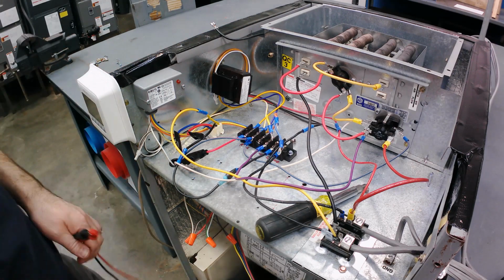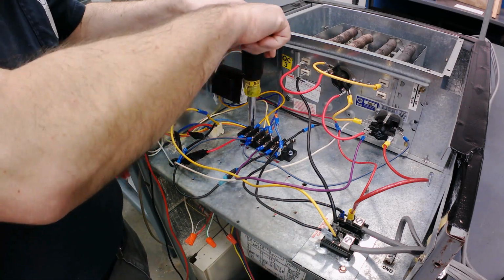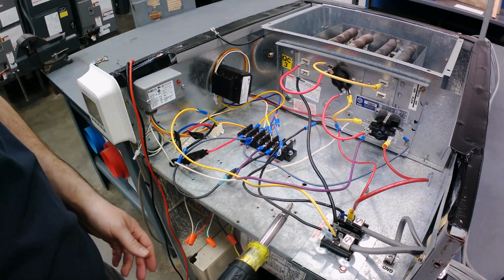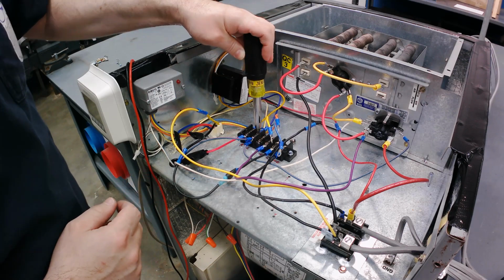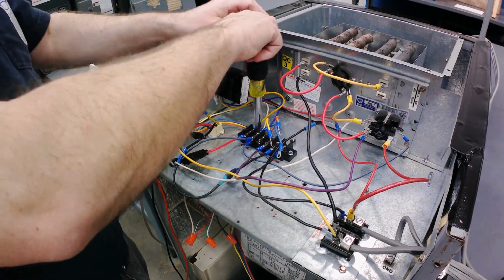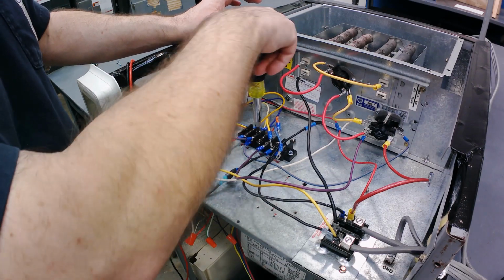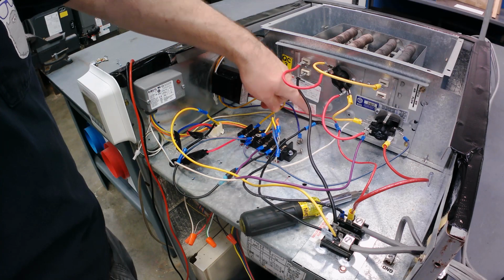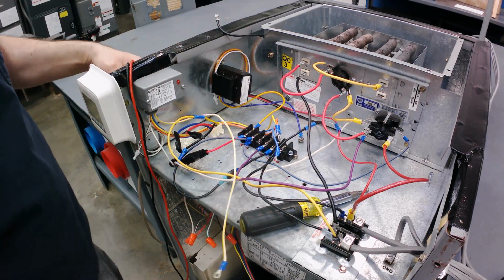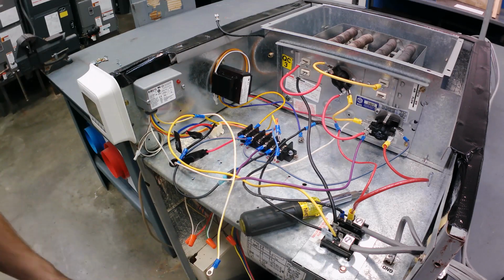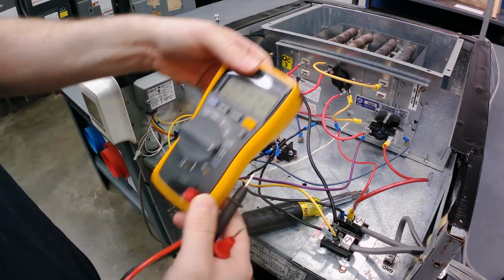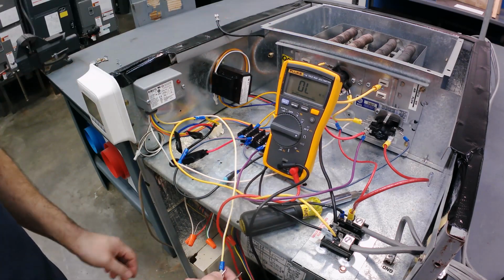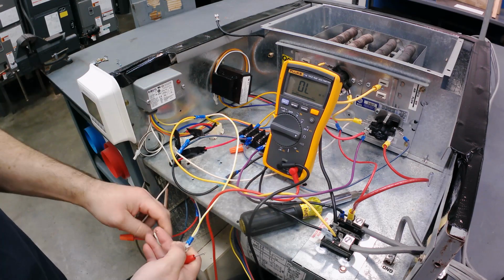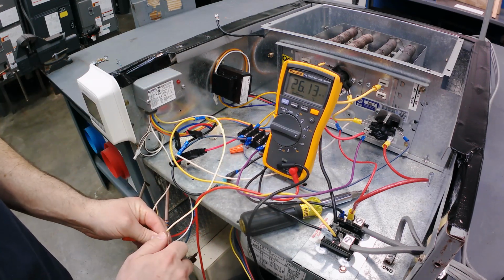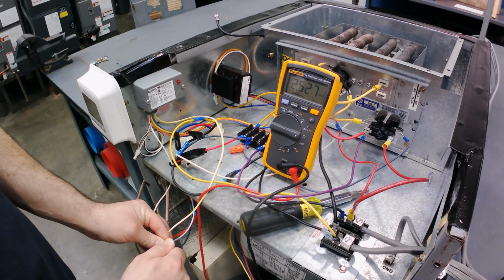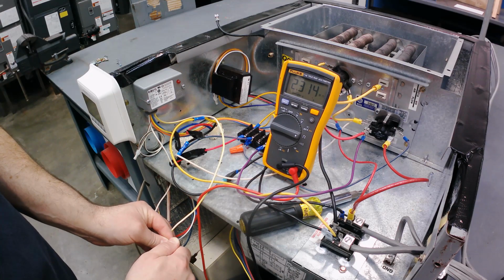are still applied to this. What I am going to do is check the coil resistance. Since I know there's a circuit board in there, I'm going to check and see what it says. In the past, when I've checked solid state controls for continuity, you get these weird readings, or what some people would consider weird. So I'm going to put this on ohms, and I'm going to ohm out from here to our connection for the green. Yeah, and I get like 2.3 mega ohms.